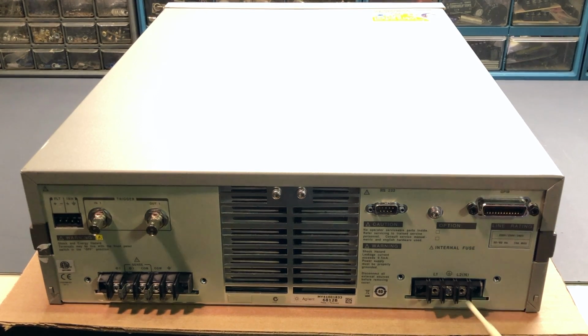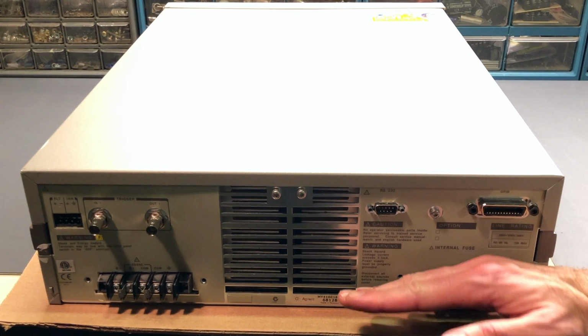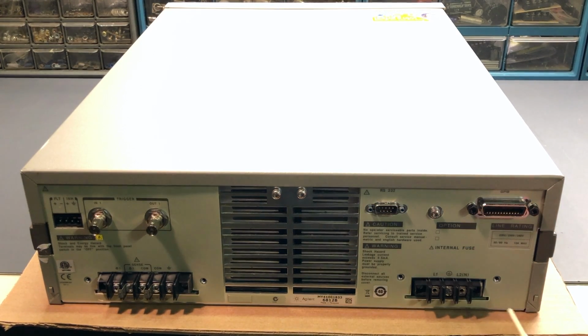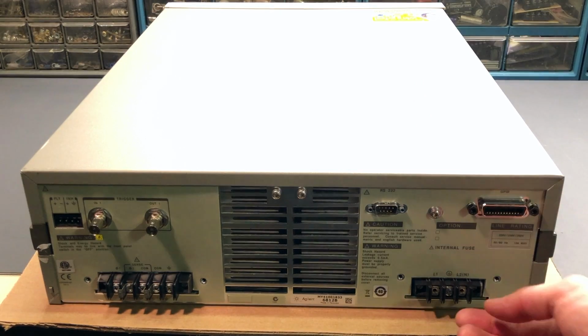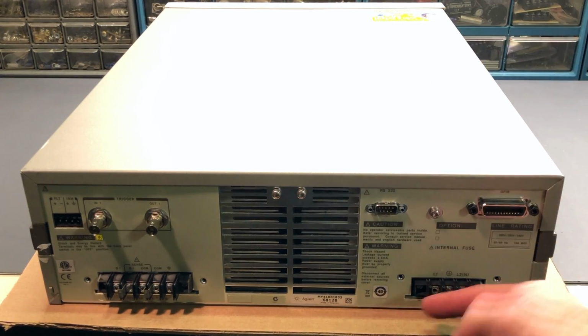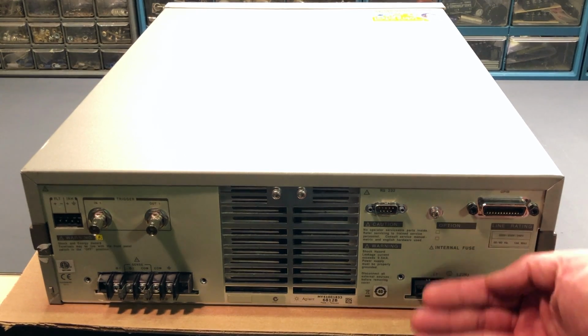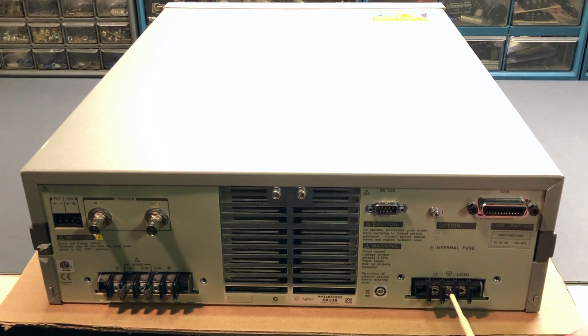Now, somewhat of a concern is that this terminal board has an upwards bend or twist to it, so it might be a little bit hard to see on camera, but it's bent or twisted upwards like this. So I need to make sure that there's no damage to the circuit board that this is attached to, and you can actually see that circuit board right underneath here. So I need to look for any cracked solders or any issues like that that are going on, and I'll do that once the top cover is removed and we have access to this circuit board or the assembly that this is attached to. Now sometimes these terminal boards can get bent like this one is because the instrument gets raised upwards like so, and the weight of the instrument presses on this as this is raised up. You know, this is the first thing that gets pressed or hit on the back side because it sticks out the furthest. So it's not uncommon to see these get bent a little bit, but again, you need to make sure that there's no damage to the circuit board or the solder connections.